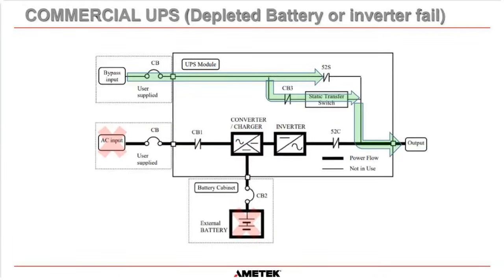And then if that battery depletes all the way down to its low voltage level, then the UPS is going to switch over to bypass. It says, okay, my battery is getting too low now. We have to do something about it. And what it does is it switches off the inverter. It will probably trip this battery breaker here. And before it does all of that, it will transfer the system using this static transfer switch here immediately to the bypass supply. You will be on bypass supply once the battery has depleted.